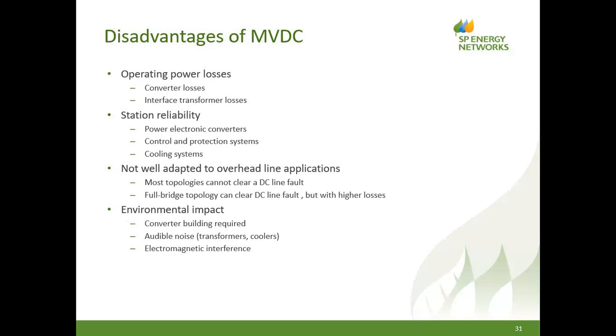Of course, there are some disadvantages which we should be aware of, and we'll evaluate these during the project. Operating power losses. We have losses in the converter technology. We've introduced a power electronic converter at both ends of the link. It was never there before. So the losses of the converters must be considered. And we've put in two new transformers that were not there before. So the interface transformer losses, i.e. the total scheme losses, must be considered.